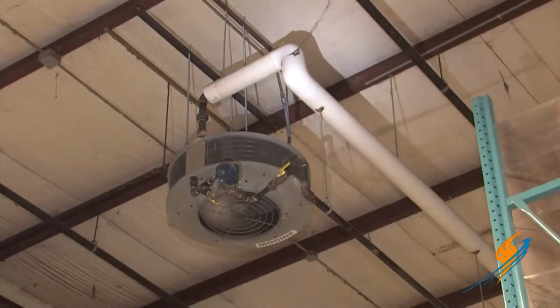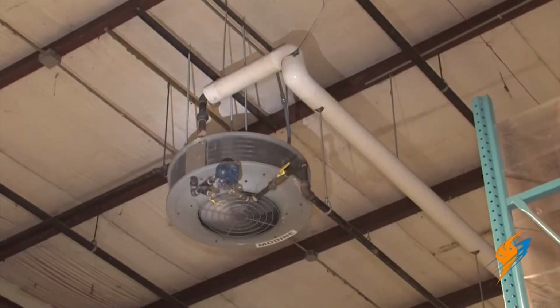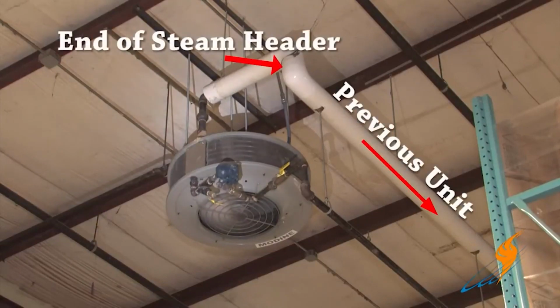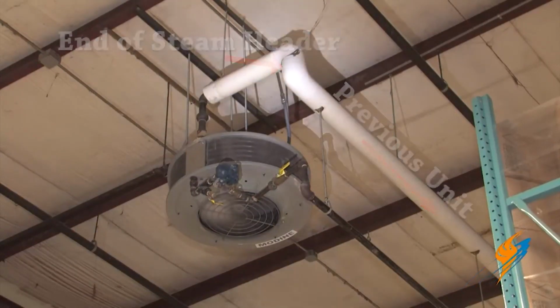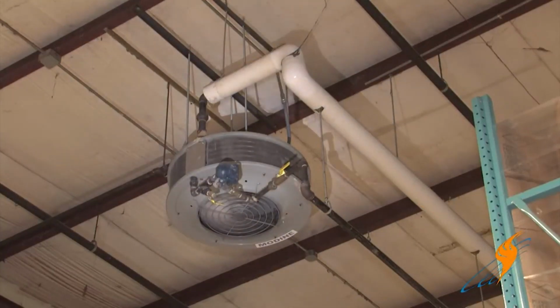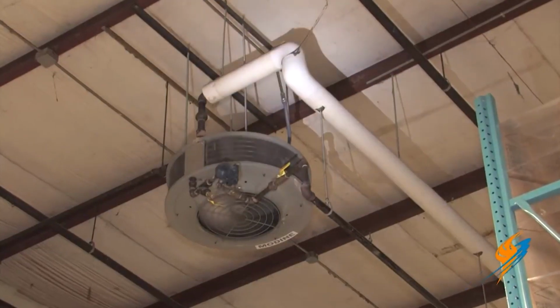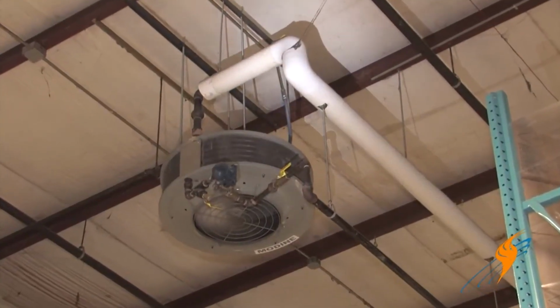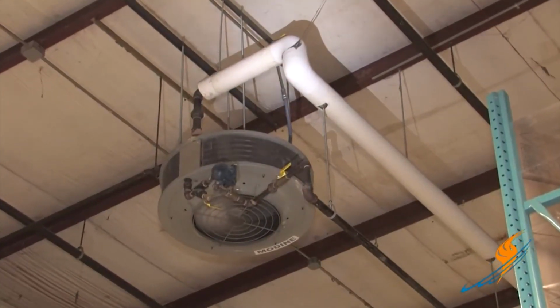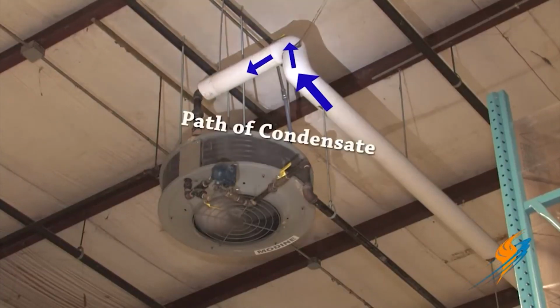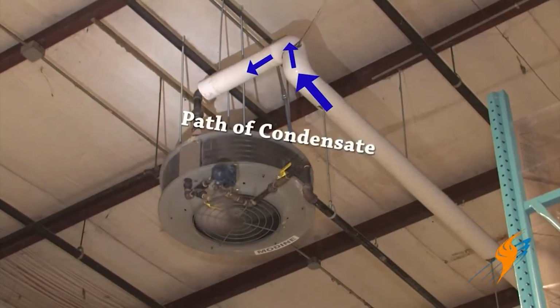This is an example of another unit, second one right down the header from the unit that we just looked at, and it's piped pretty much identically. However, we have a small problem here. Our header, and this is the end of the line here, does not have anywhere for condensate to go except for up and into the heater.